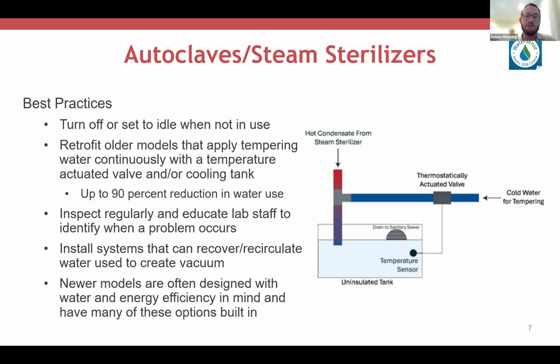There are also systems or retrofits out there that are capable of recovering and recirculating water used within the vacuum systems. So look into those if you're looking for retrofits. Also, if your autoclaves or sterilizers are getting up there in age, I would consider replacing them. Older models have a lot of these quirks and high water use, but newer models will typically have built-in tempering water control, built-in water circulation, or at least options to purchase those when you're procuring.